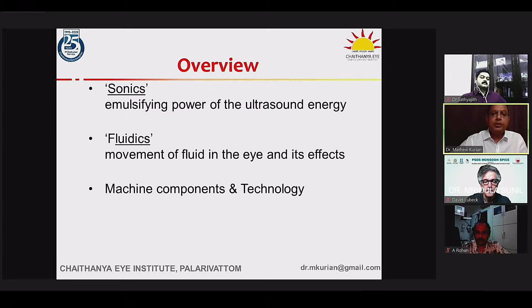Before we start anything with the machine, before the patient even comes into the theater, we need to do what is called priming and tuning. Priming is our check of the fluidics, where we test for leaks or blockages in the system, and this is critical to get rid of any air in the tubing or the cassette. Why? Because residual air increases the compliance and reduces your system performance. So you might have a fantastic machine, but if there is air in the tubing, it will not work anywhere near your expectations.